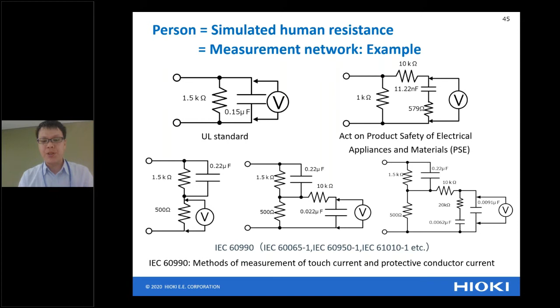Okay. So from the standard, leakage current tests are defined so as to allow confirmation of how much leakage current will flow under a variety of circumstances. The test must be carried out under a number of test conditions. So it means we have to do two kinds of situation: normal condition and single fault condition. As I told you, a medical device should have a very, very high class of safety. So that's why even under a single fault condition, like supply voltage increased by 110%, a break in the power wire, and a break in the ground wire, even under this kind of single fault condition, a medical device has to be safe.